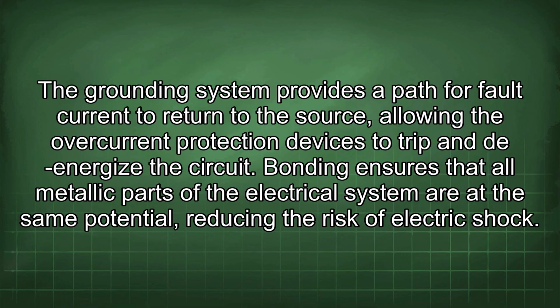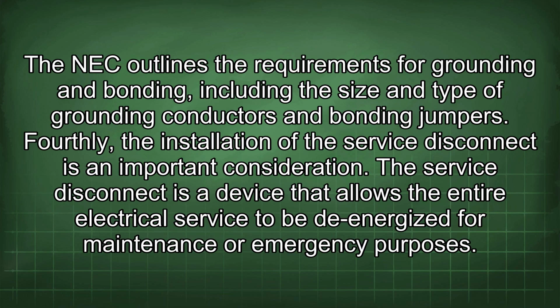The grounding system provides a path for fault current to return to the source, allowing the overcurrent protection devices to trip and de-energize the circuit. Bonding ensures that all metallic parts of the electrical system are at the same potential, reducing the risk of electric shock. The NEC outlines the requirements for grounding and bonding, including the size and type of grounding conductors and bonding jumpers. Fourthly, the installation of the service disconnect is an important consideration.